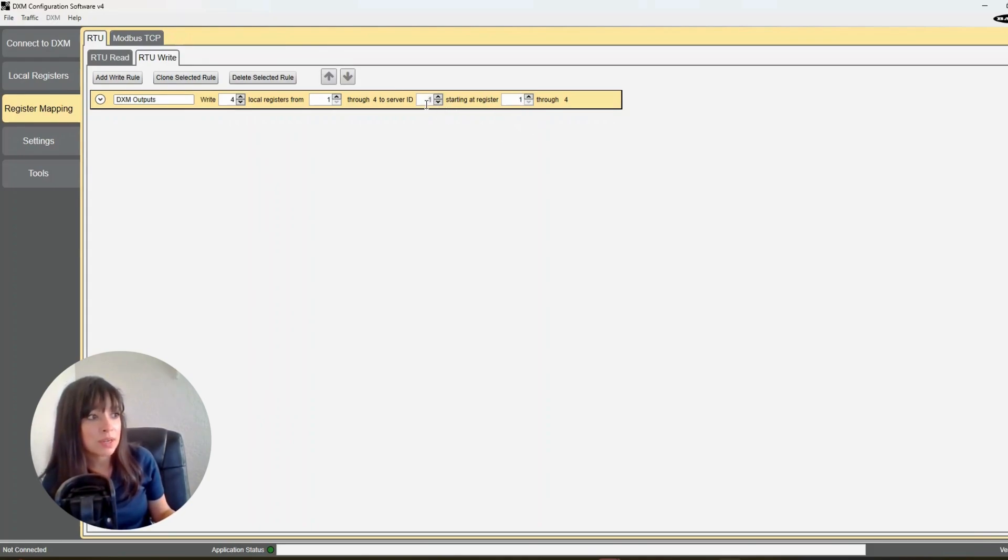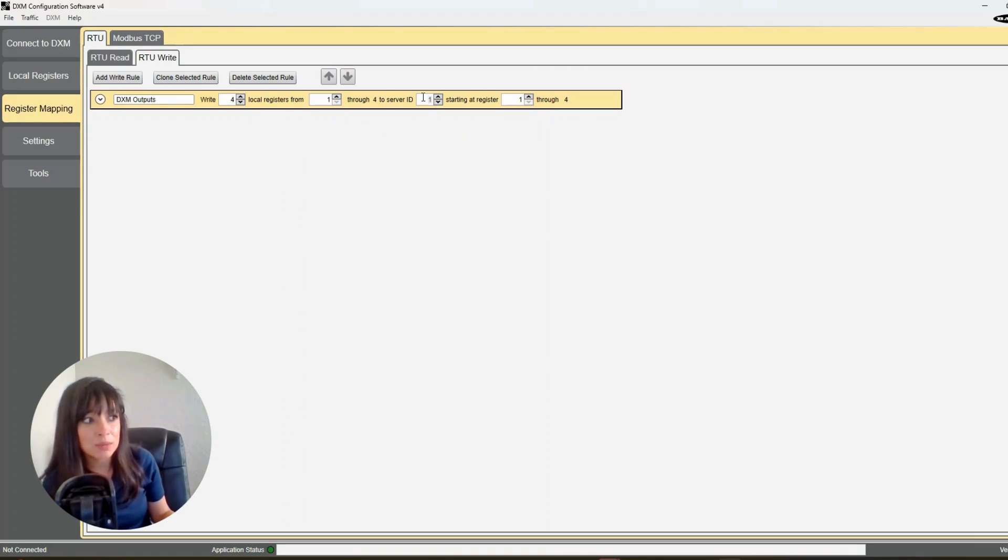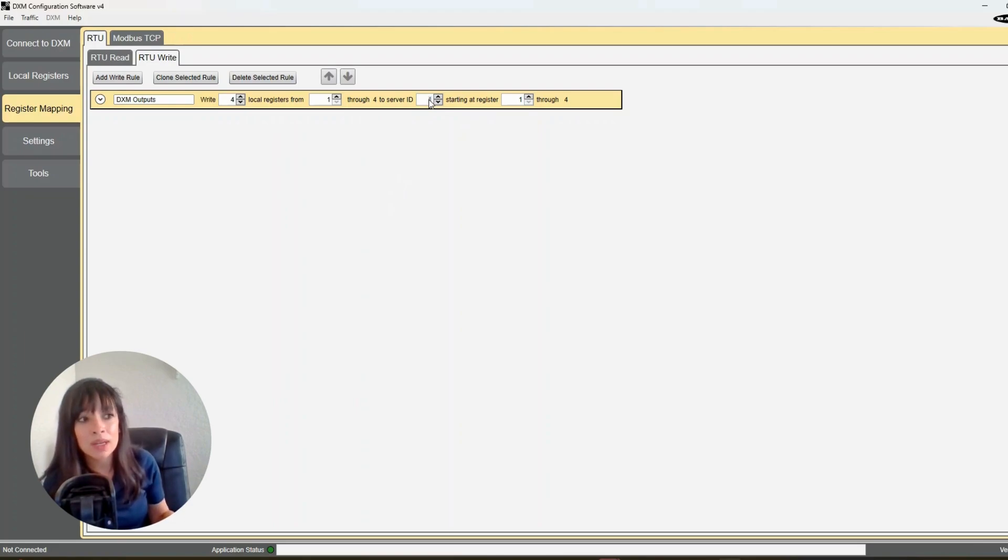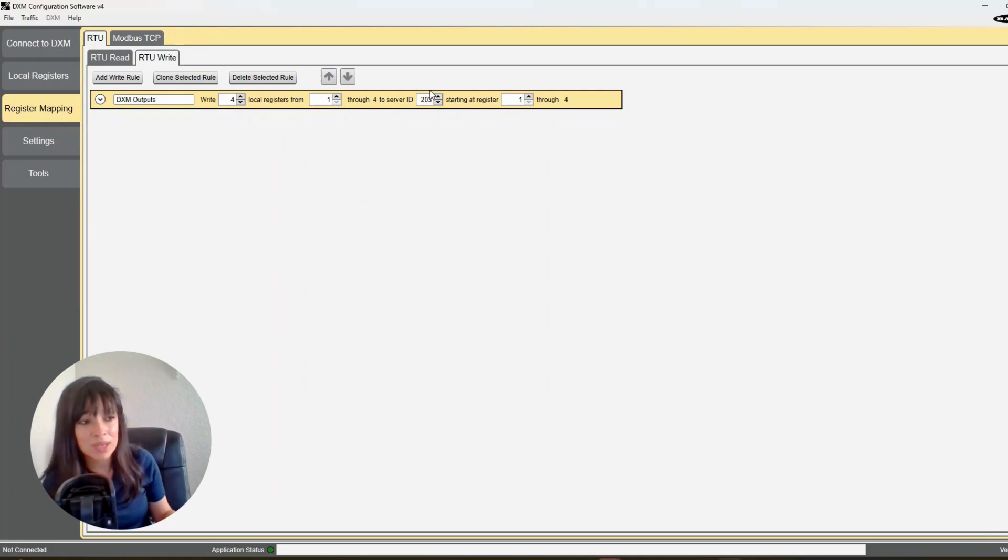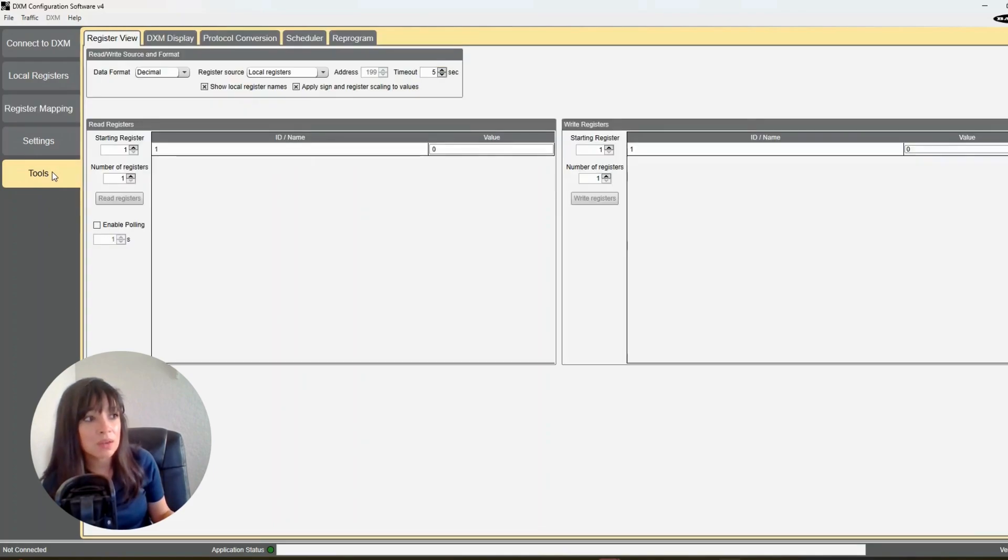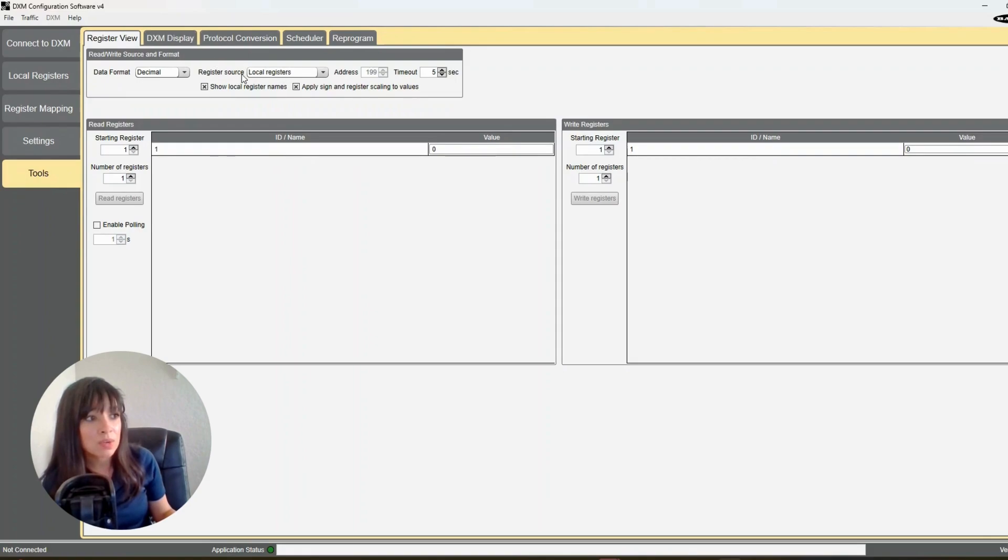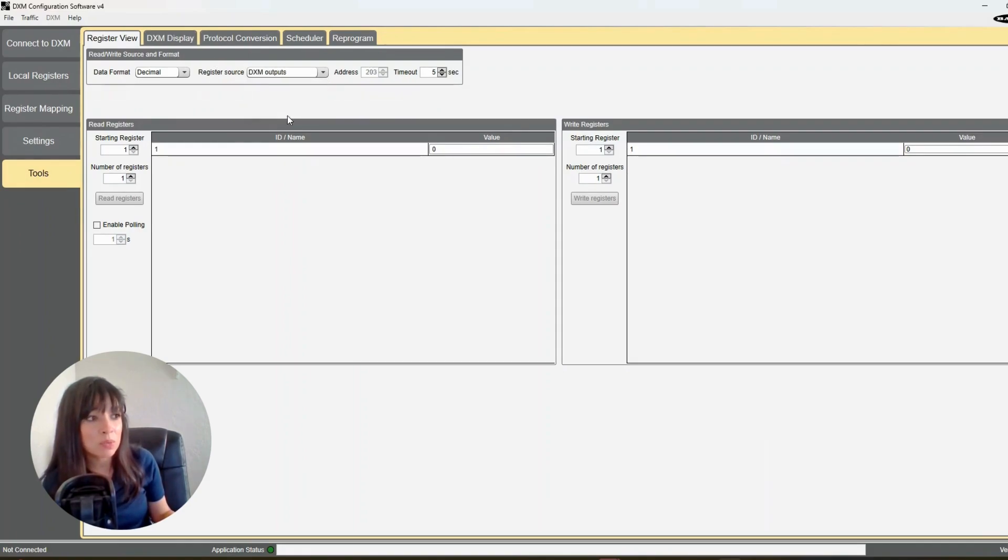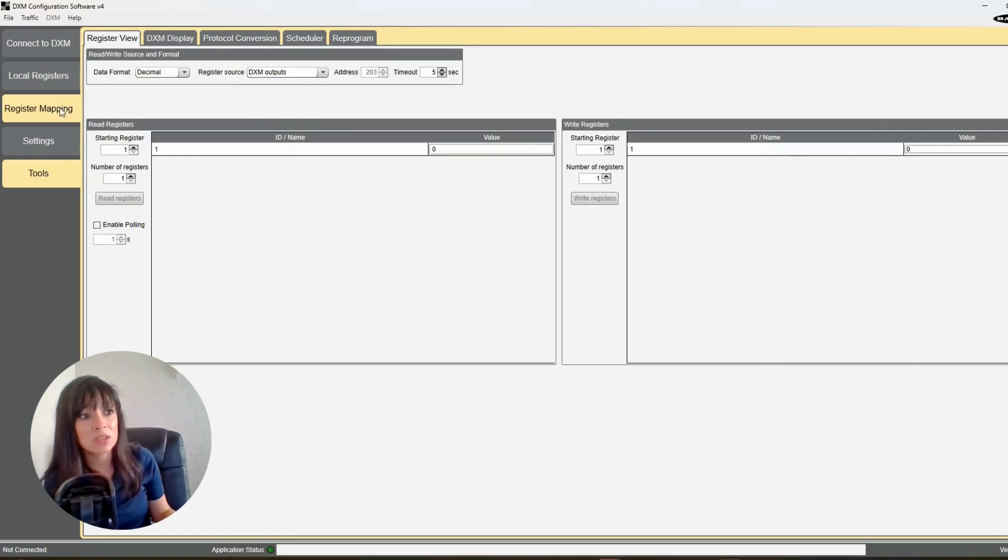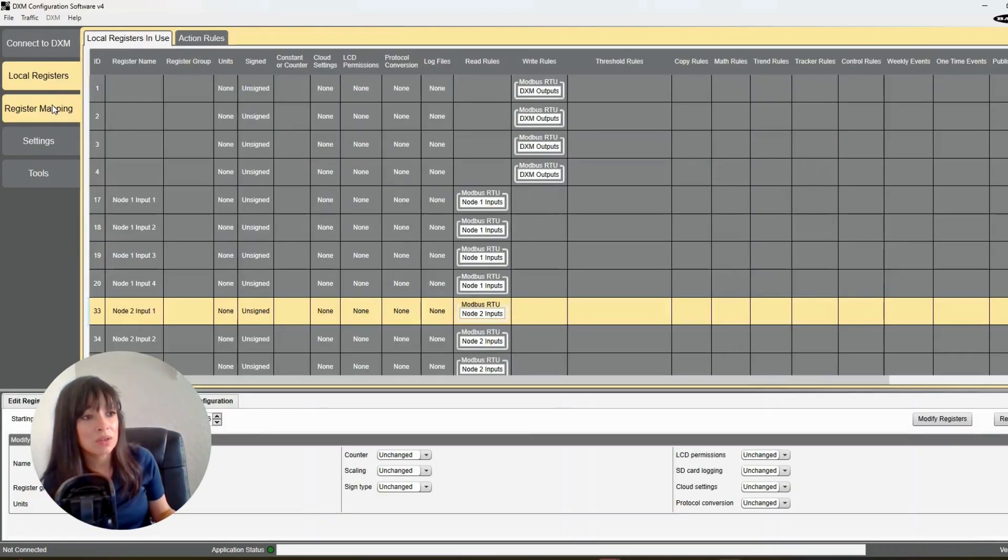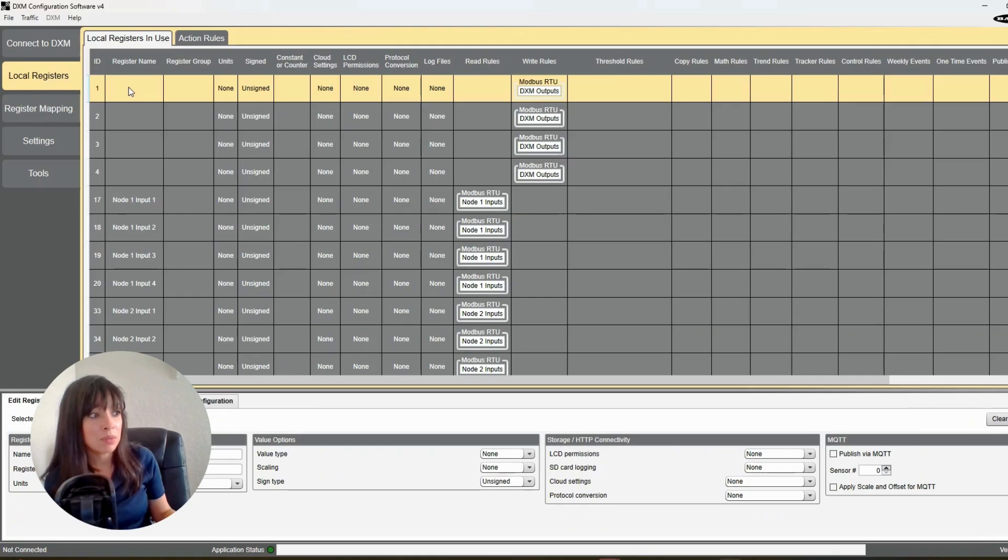The DXM outputs are located on a different board, which puts us at an address of 203. How do I know this number? Well, it's in the manual if you read long enough, but a shortcut would be to go to your tools, register view, go to register source, and if you click on DXM outputs, it'll pop up your address. So we're going to look at address 203 there. So that's a big gotcha if you don't know how to do that or you didn't know that, that might be a problem.